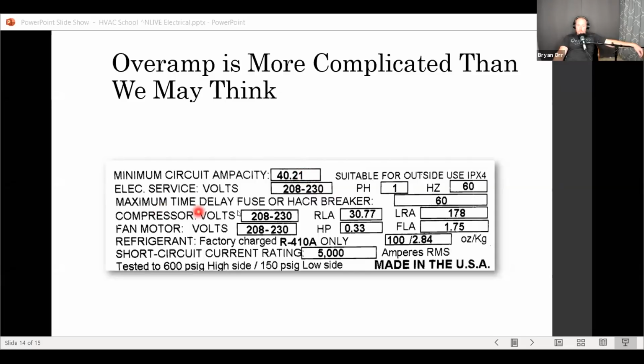And then you find the breaker. You can connect up to a 60 amp breaker. Now, you could go down to the size of the wire ampacity. You can go down. Now, you may have nuisance trips, but you cannot go above this. So you can put a 60 amp breaker on a wire that's designed to carry 40.21. And people will say that is complete heresy. You're going to burn down a house. No, you're not, because this appliance has an overload built into all of the motors that will shut them off before you have a consistent overload condition that could melt the wire.